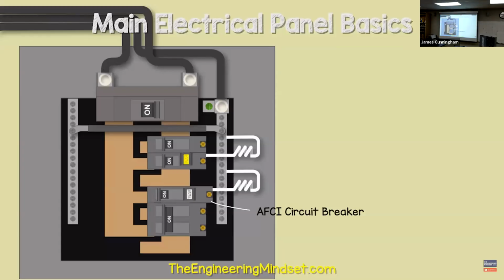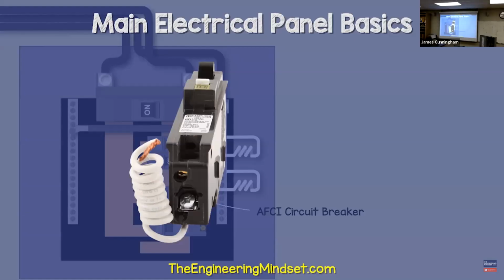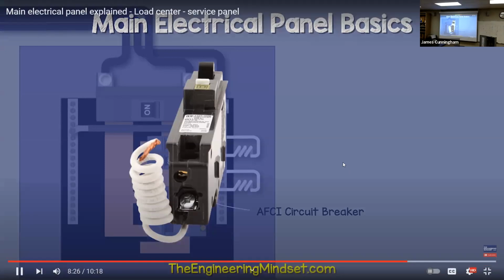We might also come across an AFCI circuit breaker. This stands for Arc Fault Circuit Interrupter. These are required for circuits feeding bedrooms, hallways, kitchens, etc. Again, check. All the outlets now and lighting circuits are required to have arc fault in our new panels.